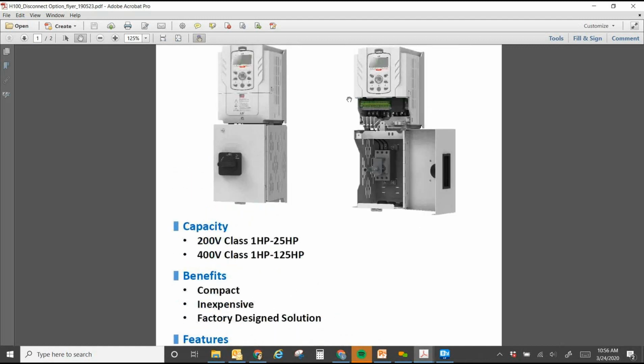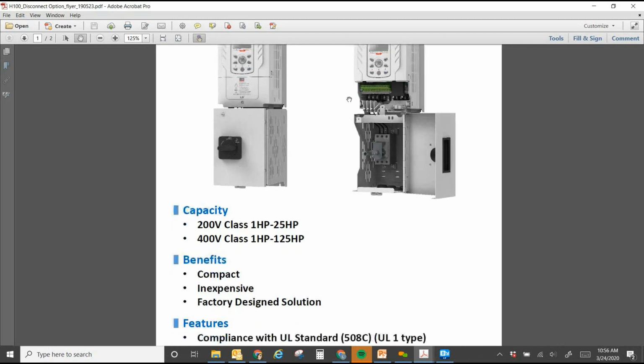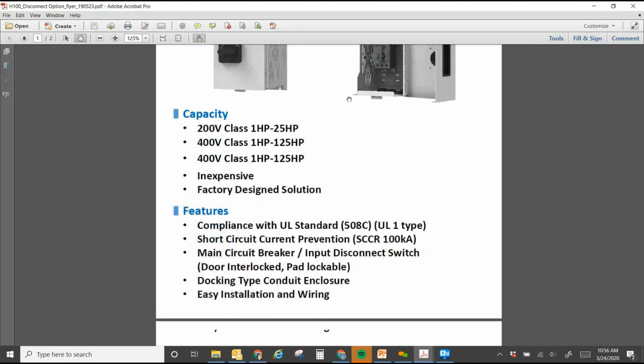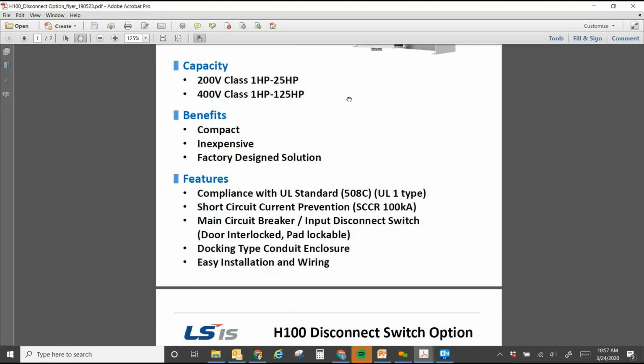It's all LS stuff, so this one has an LS MMS on there, a manual motor starter. Once you hit the larger sizes, there's a built-in circuit breaker. This meets UL 508C, it's a UL Type 1 rating, and the key thing most of you would care about with HVAC stuff is the short circuit current rating is 100K.